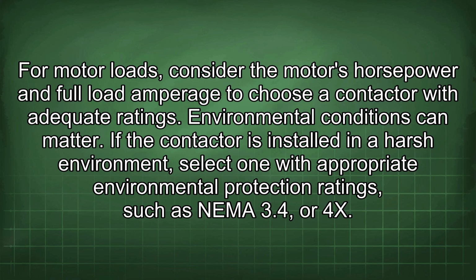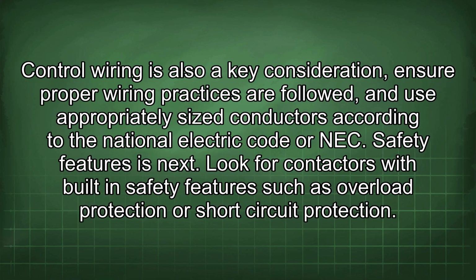Environmental conditions can matter. If the contactor is installed in a harsh environment, select one with appropriate environmental protection ratings such as NEMA 3, 4, or 4X. Control wiring is also a key consideration. Ensure proper wiring practices are followed, and use appropriately sized conductors according to the National Electrical Code, or NEC. Safety features are next. Look for contactors with built-in safety features such as overload protection or short-circuit protection.